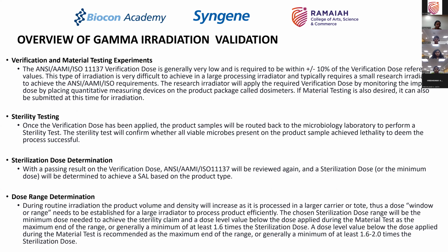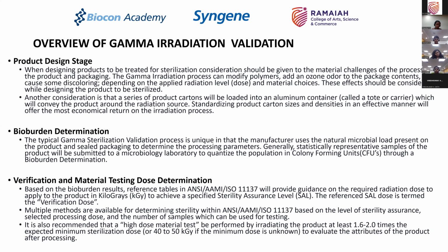Now, once you have done this verification, you decide what should be the sterilization dose based on the sterility assurance level. So, when we go through the steps, you first study the product. This is all polymer chemistry and designing the product right: how you're going to package it, and what is the initial bioburden expected in the material under normal conditions.